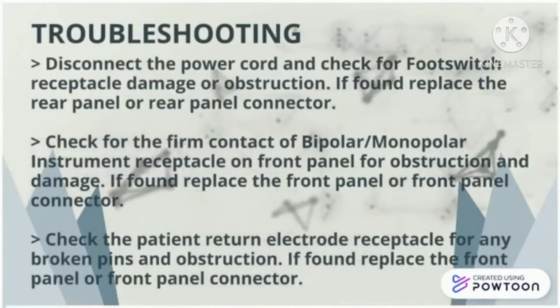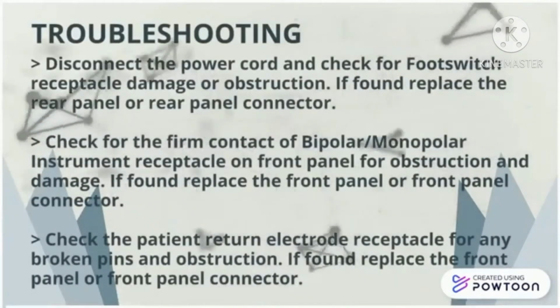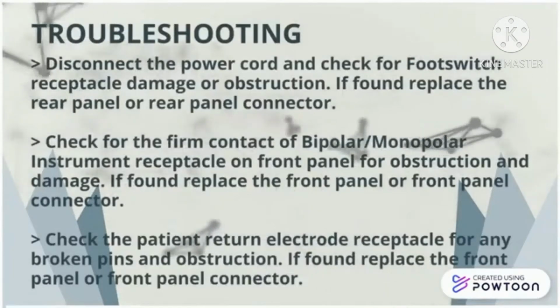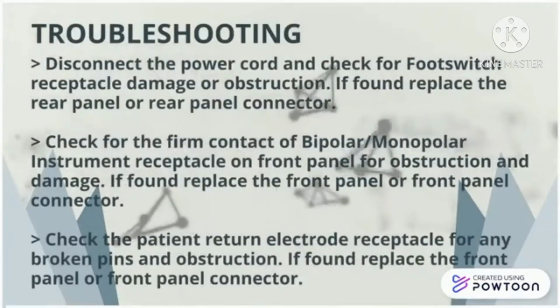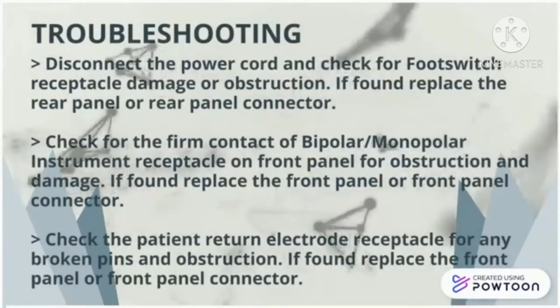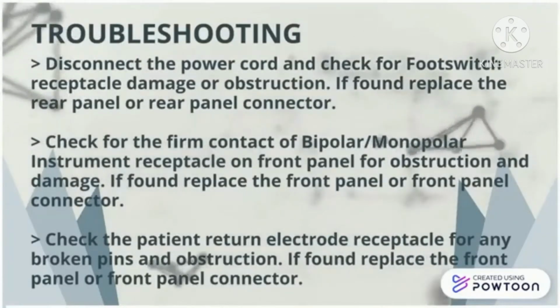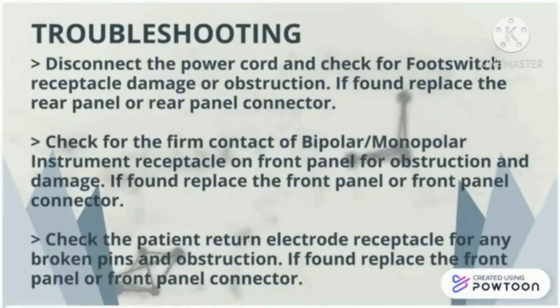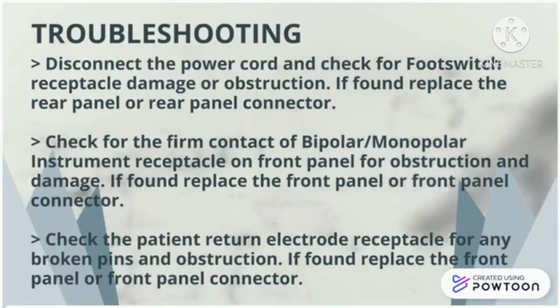Disconnect the power cord and check the Footswitch receptacle for damage or obstruction. If found, replace the rear panel or rear panel connection. Check for the firm contact of Bipolar/Monopolar Instrument receptacle on the front panel for obstruction and damage. If found, replace the front panel or front panel connection. Check the patient return electrode receptacle for any broken pin and obstruction. If found, replace the front panel or front panel connection.